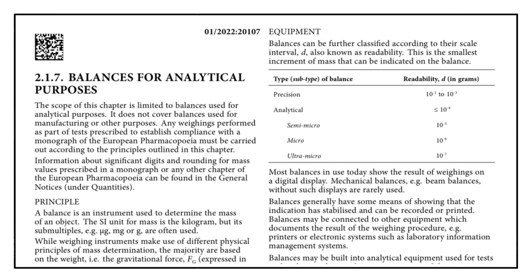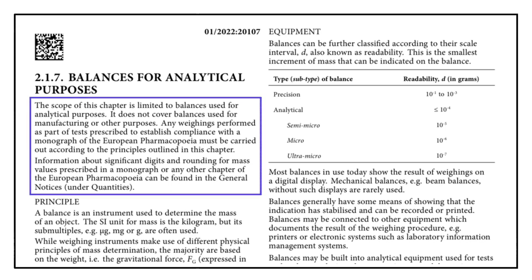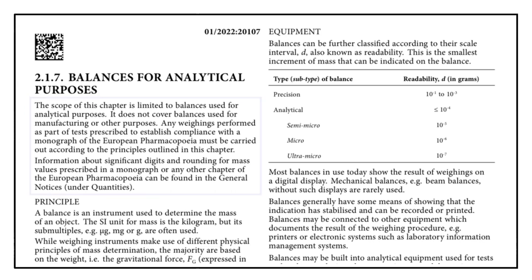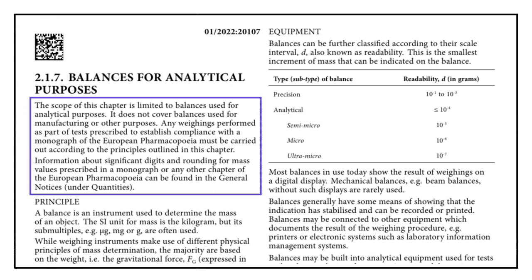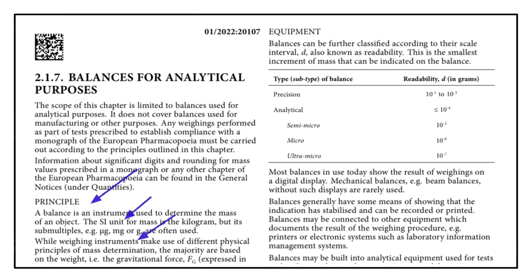The very first line of EP chapter 2.1.7 states that this chapter is only applicable to balances used for analytical purposes. It does not cover balances used for manufacturing or other purposes. In simple terms, this chapter is applicable to the quality control laboratory only. Now let us begin by looking at the principle of analytical balances.